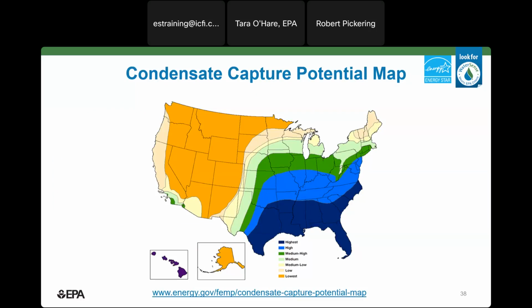The Federal Energy Management Program, or FEMP, has created a really nice resource to help facility managers determine the potential for condensate capture. As you can see, facilities in the Southeast, Midwest, and Mid-Atlantic all have really high potential for collecting condensate for these types of projects. That being said, really cost-effective projects can be available anywhere, provided that your air handlers are in close proximity to cooling towers. FEMP also has some really nice maps for rainwater potential, as well as reclaimed wastewater availability, which are two other potential sources of cooling tower makeup water.